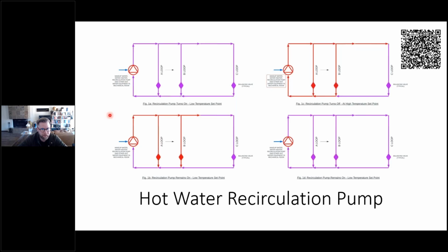pathogen outbreaks and a number of litigations surrounding that, is when you add an aquastat to the pump and you turn off the pump when you meet the temperature, there is a potential in your most hydraulically remote loops that you end up in a situation where you never get out of Legionella growth temperature. So here's an example: there's a low temperature set point, so the pump turns on, and we have a system where the water is getting heated again by that symbol in the mechanical room and starts flowing out, and your A and B loops are satisfied and they jump to temperature very quickly. And especially if this is an unbalanced system, but even in a balanced system, if you have enough loops that are close, you potentially could get to your system set temperature.